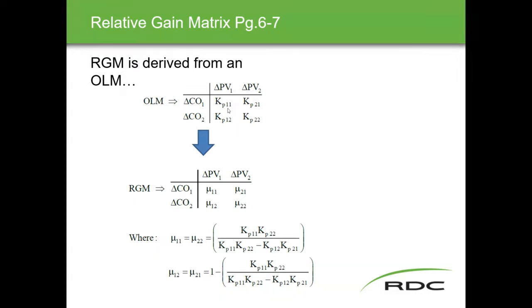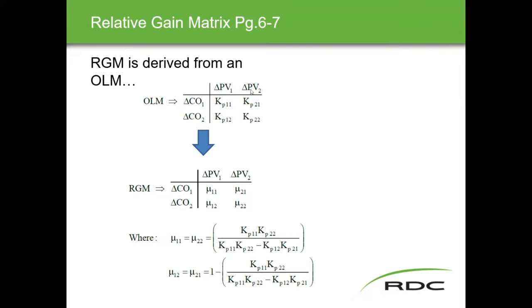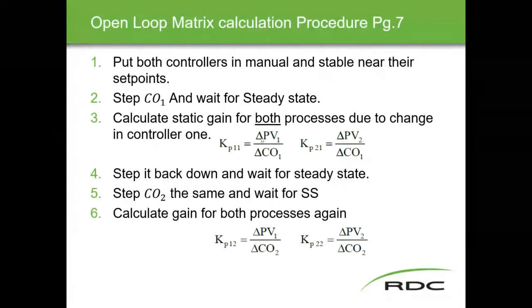To develop the relative gain matrix, we start with an open loop matrix. The open loop matrix is found by determining the static gains of the individual loops. That's the testing we do: make a 10% change in CO1, record the effect on PV1 and PV2, use the output-over-input formula, and get individual static gain values. Those values go into the formula, which gets converted into the relative gain matrix, filling it in using the associated formulas for positions 11, 22 and 12, 21.